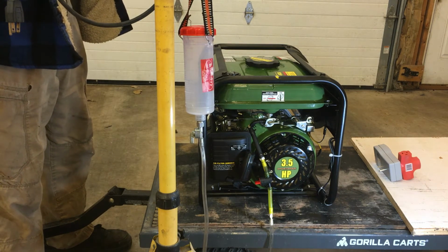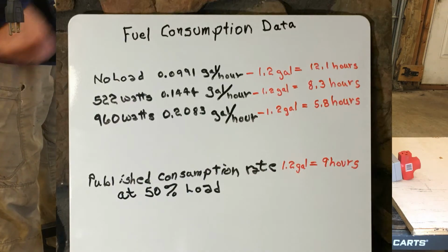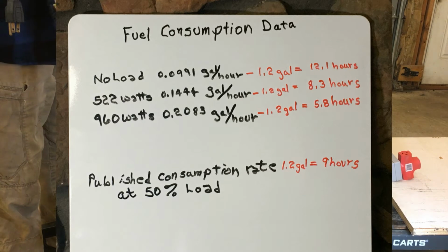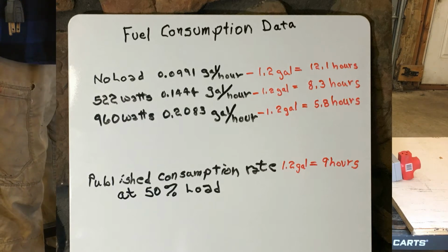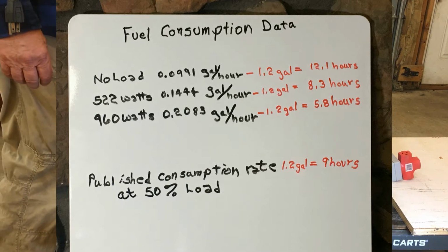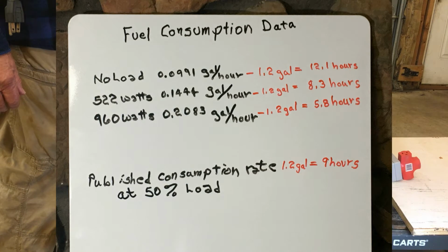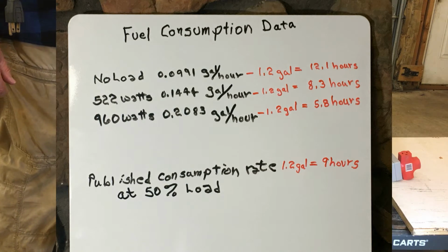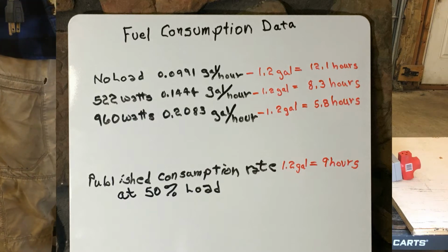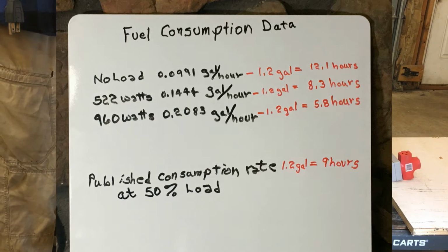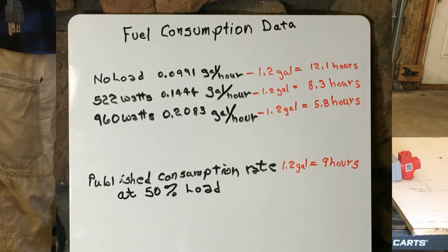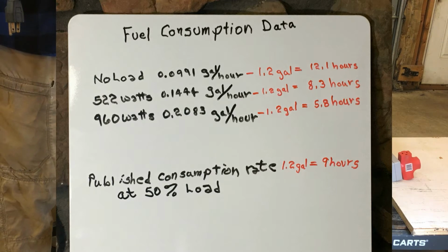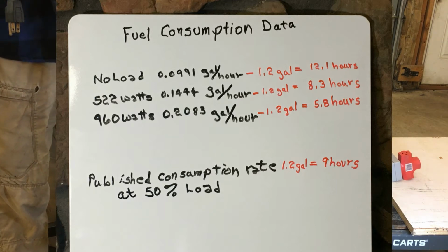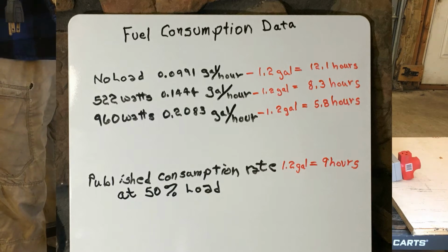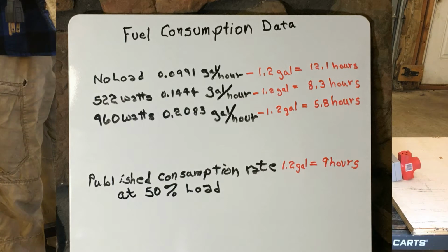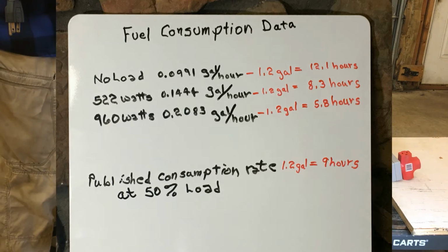In doing that, I also changed the load from a no-load condition up to 960 watts. At no load, the number I came up with was 0.099 gallons per hour. At 522 watts, the number was 0.144 gallons per hour, and at 960 watts, the fuel consumption was 0.208 gallons per hour.